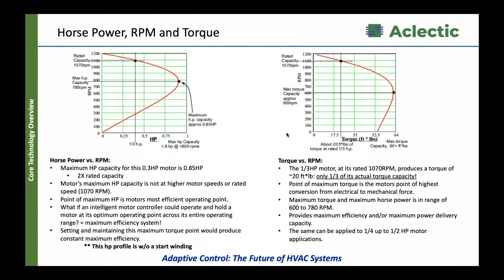Because we have the smarts, we're constantly monitoring where the slip is, where the motor is, what's happening, and thus we can move up and down that curve and optimize torque and optimize horsepower, but not cause problems to the motor while doing it. And that's all we're highlighting here. So we'll move on there because probably.